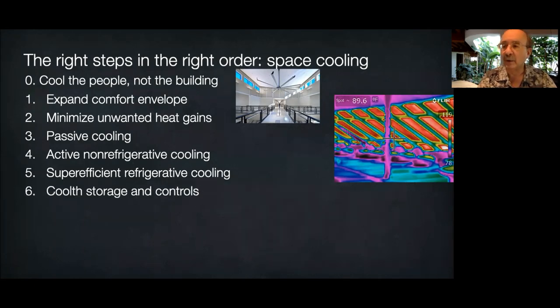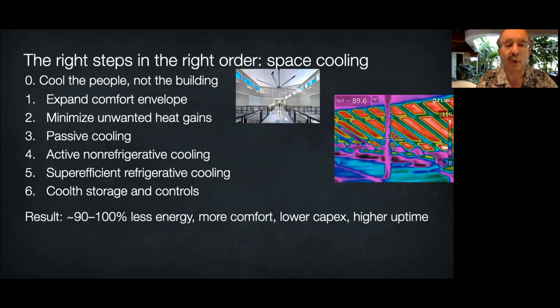We exploited all six classical comfort variables — including excellent ceiling fans that gain 5 to 7°C of comfort range, and super windows that slashed radiant loads. We rigorously reduced unwanted internal and external heat and humidity gains, and recovered 93% of ventilation heat or cool. Like an Aspen skier dressed in a down jacket and sunglasses, the building is nearly twice as airtight as a passive house, super-insulated, and passively cooled by active exterior shading and natural ventilation including automated night flush. So even in the worst climates — Bangkok, Singapore — this comprehensive approach can save around 90 to 100% of cooling energy with better comfort, lower capital cost, and higher uptime.